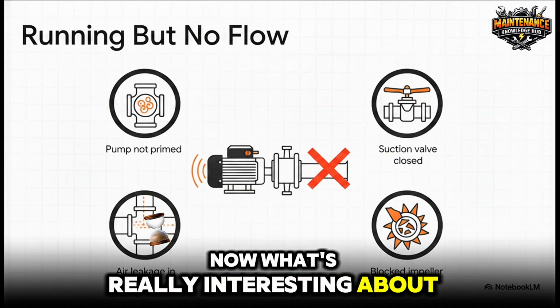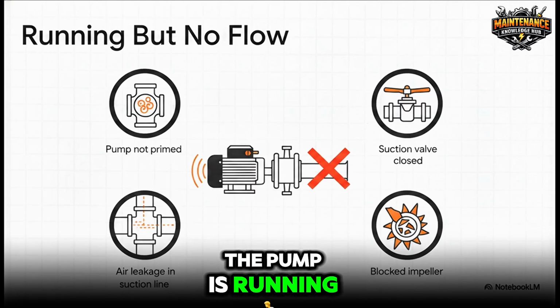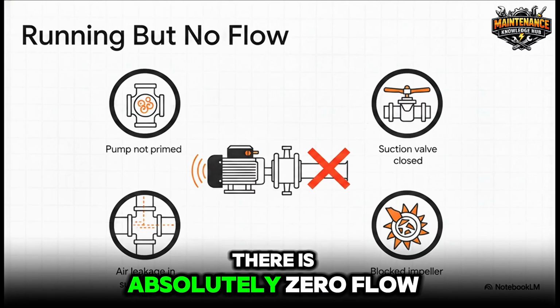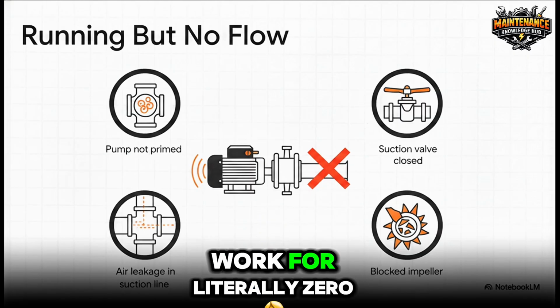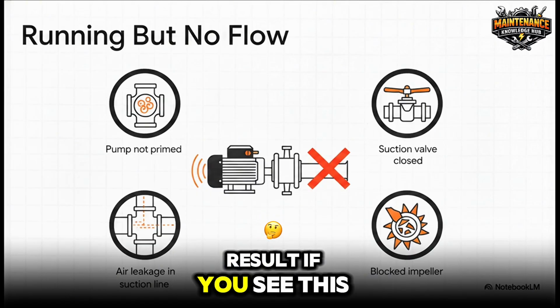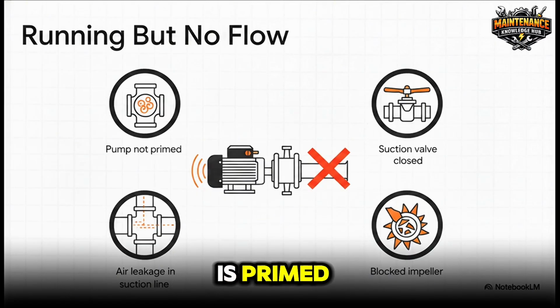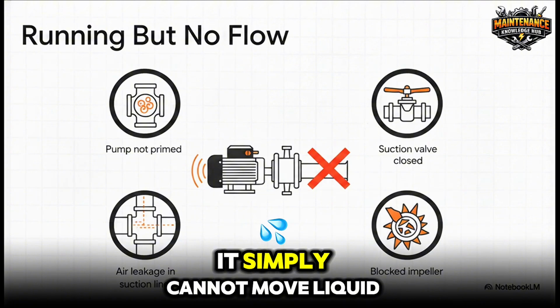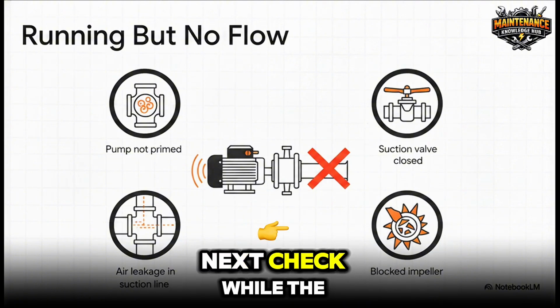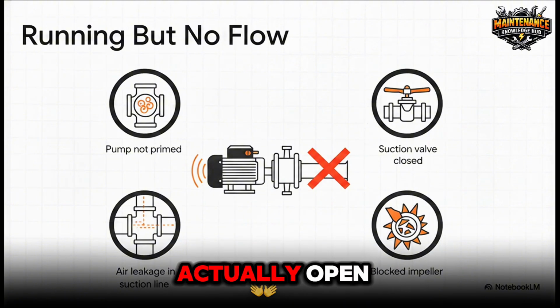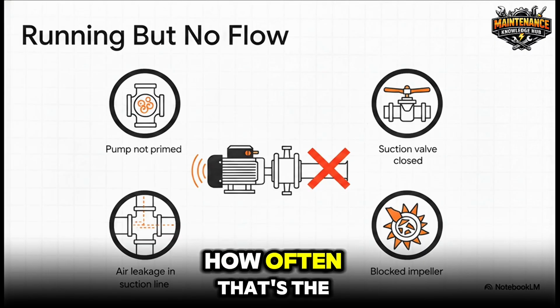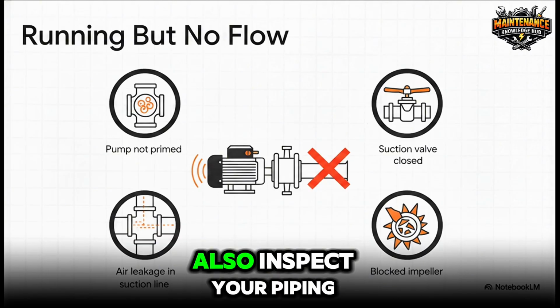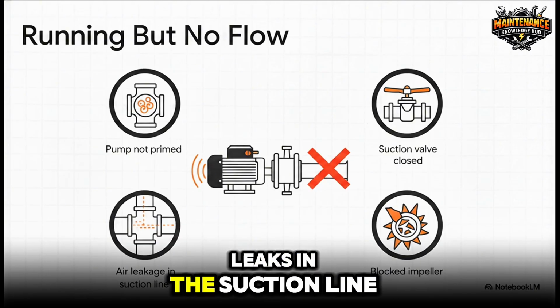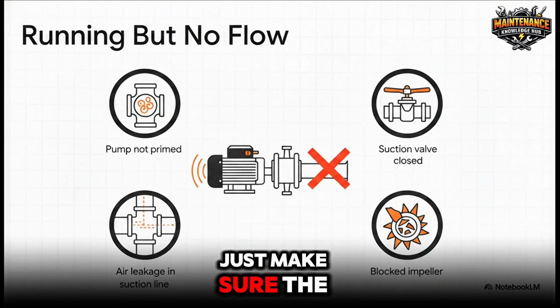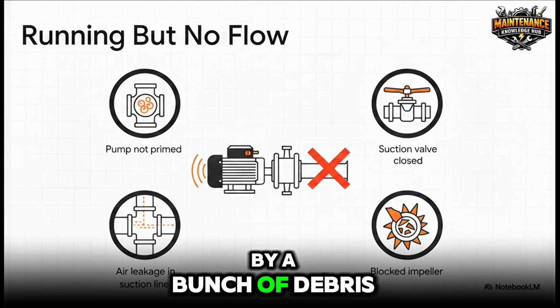Now, what's really interesting about all this is what happens when the pump is running. The motor's spinning, but there is absolutely zero flow. It's doing all the work for literally zero result. If you see this, first check if the pump is primed. If there is air trapped inside, it simply cannot move liquid. Next, check the wildly obvious: is the suction valve actually open? You would be amazed how often that's the real culprit. Also, inspect your piping joints for any air leaks in the suction line, and lastly, just make sure the impeller itself isn't blocked by a bunch of debris.